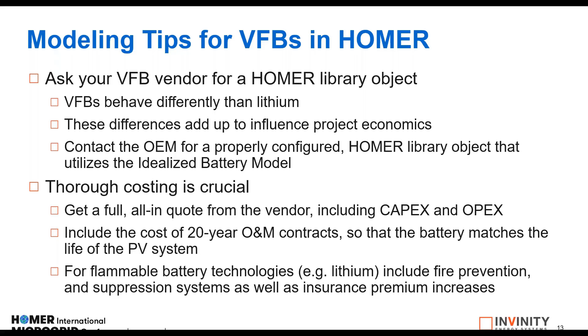And finally, if one of the battery technologies is a flammable type, such as lithium, then it's important to do the due diligence and find out what the additional cost of any fire prevention and suppression systems is, what the effect may be on the customer's insurance premiums, and what, if any, modifications are necessary to make sure the fire prevention and suppression systems identified have been properly integrated with the lithium-ion system.